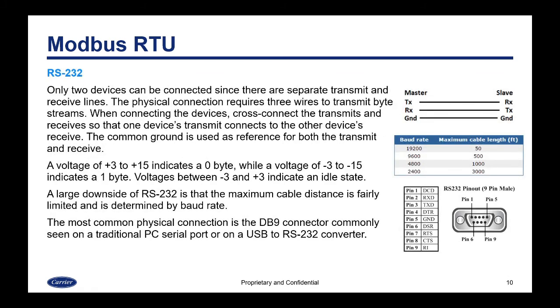With Modbus RTU, the first variety is RS-232. With RS-232, only two devices can be connected since there are separate transmit and receive lines. The physical connection requires three wires to transmit byte streams. When connecting the devices, cross-connect the transmit to the receive and the receive to the transmit, so that one device's transmit connects to the other device's receive. The common ground is used as a reference for both. A voltage of plus three to plus fifteen indicates a zero byte, while a voltage of minus three to minus fifteen would indicate a one byte.